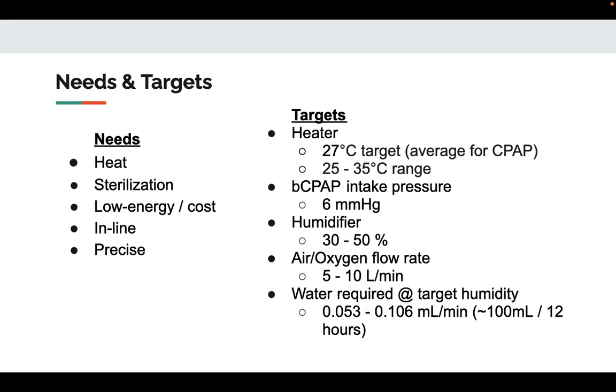The targets are a heater, which needs to be able to hit 27 degrees Celsius, which is an average for CPAP, and needs to incorporate a range of 25 to 35 degrees Celsius at a minimum. So the bubble CPAP intake pressure is 6 millimeters of mercury, so our system needs to be able to accommodate an inflow of air at that pressure. The humidifier needs to humidify the relative humidity of the air to 30 to 50%. The air and oxygen flow rate will be 5 to 10 liters per minute through the system, and the water required at target humidity is 0.053 to 0.106 milliliters per minute, which is approximately 100 milliliters per 12 hours.